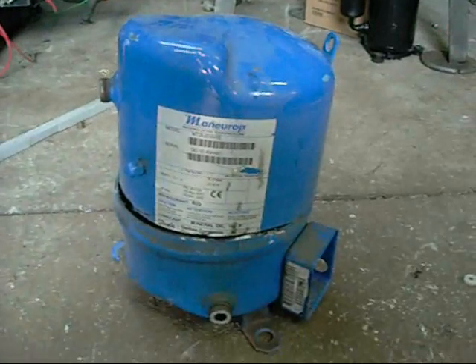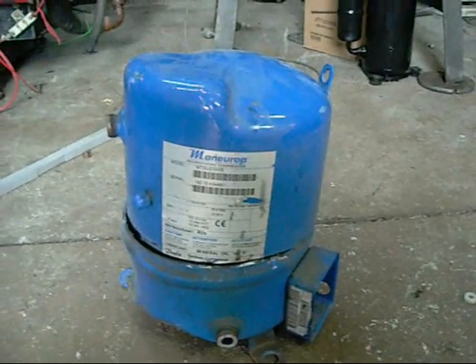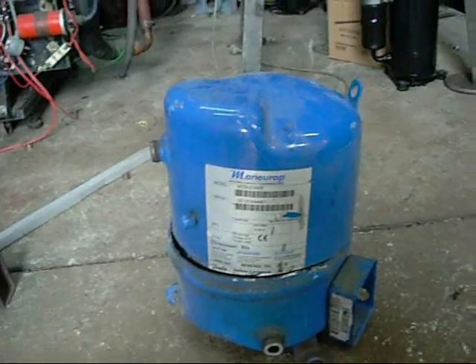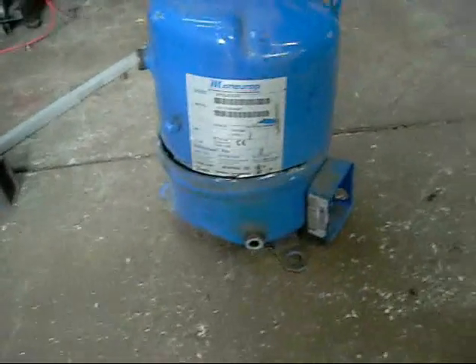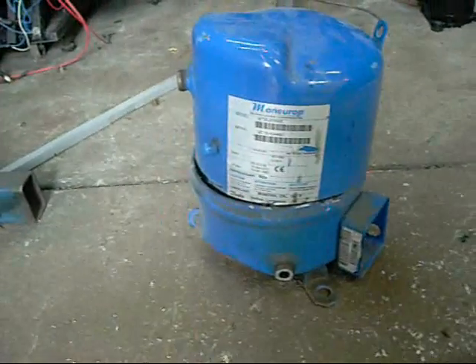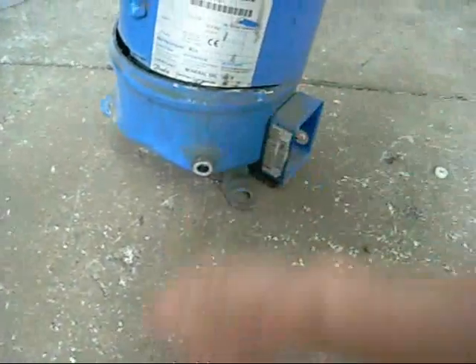G'day folks. This is a compressor autopsy on a Maneurop MT28JE 5NVE single cylinder R22 compressor, made for Danfoss Commercial Compressors Australia. It's a 240V single phase unit, 16A maximum locked rotor amps, 55 mineral oil.